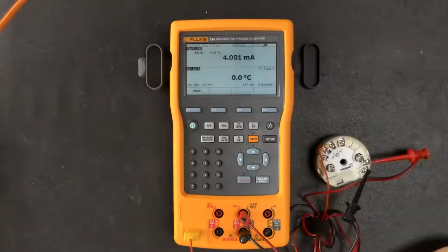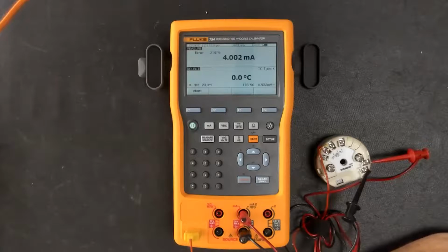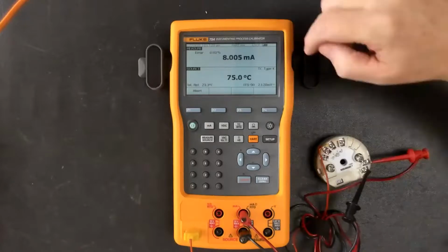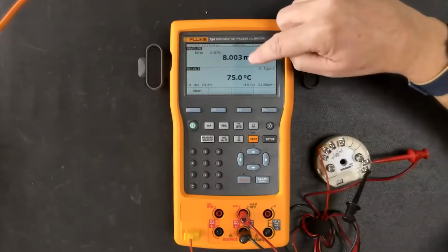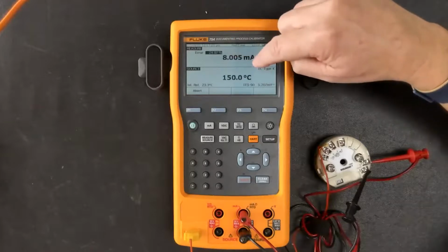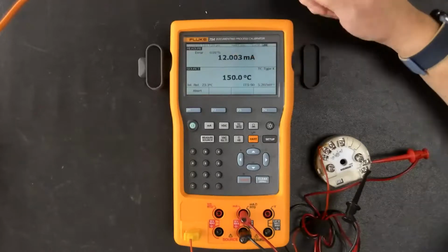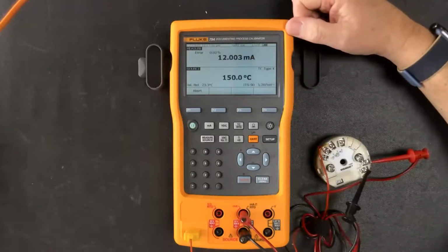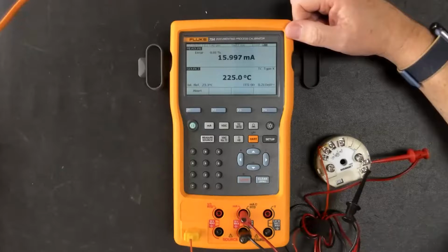So again, it's going to repeat the calibration test at the 5 different test points. Go from 0 to 75 to 150 and so forth. And it's now capturing. If you notice, you're starting to see some numbers that look a little bit better than before. And we're not going to see the inverse video anymore if we've made the adjustments, which it looks like we're doing a pretty good job here. So again, once it's completed with the as left test, this information will be captured in the calibrator.